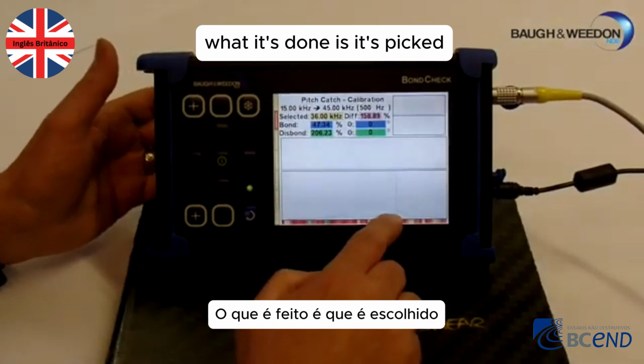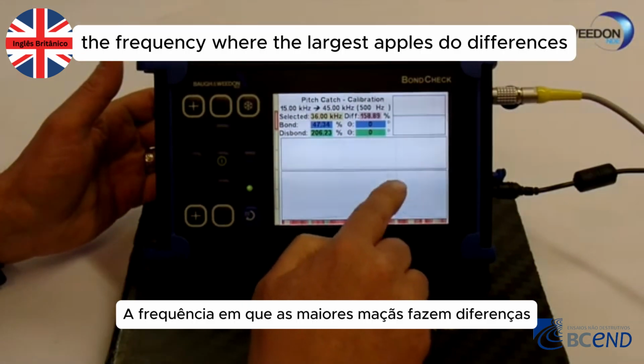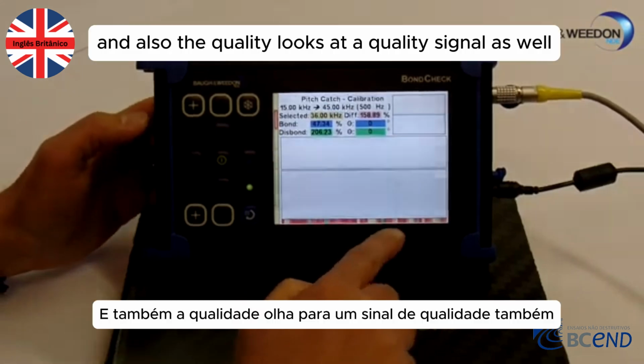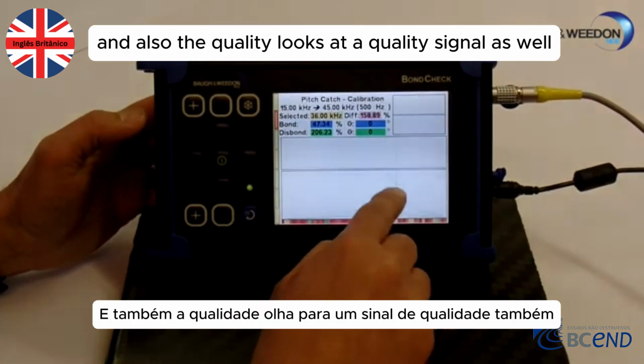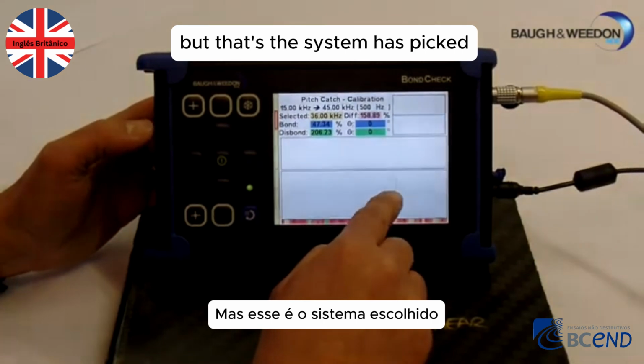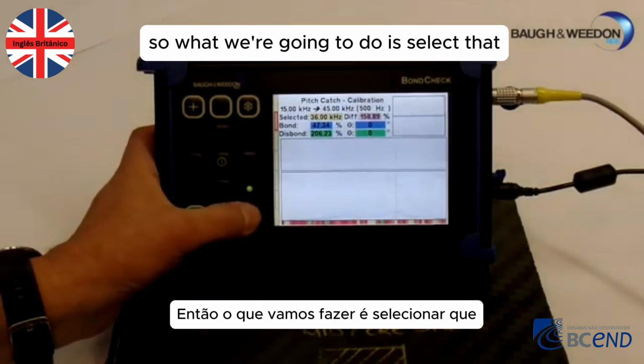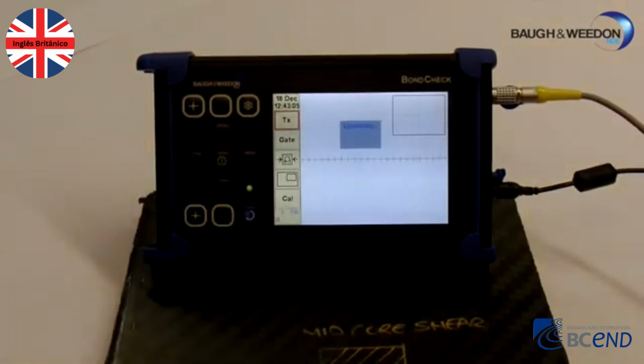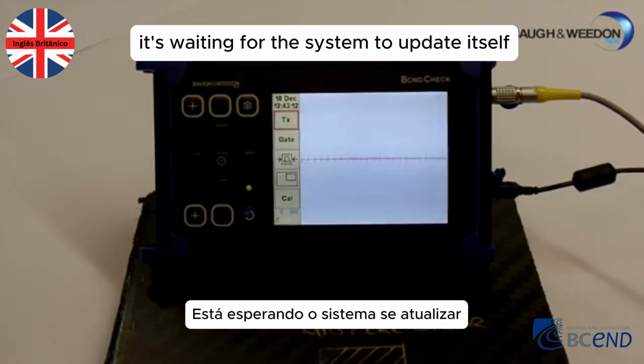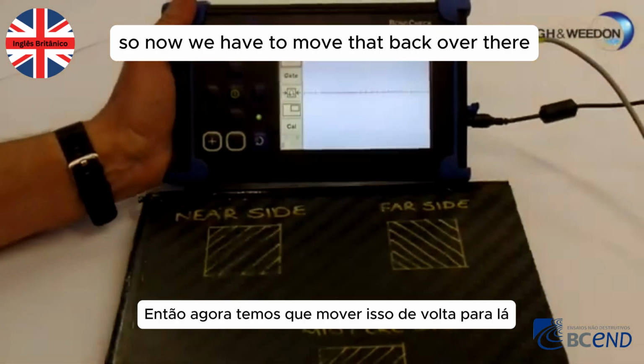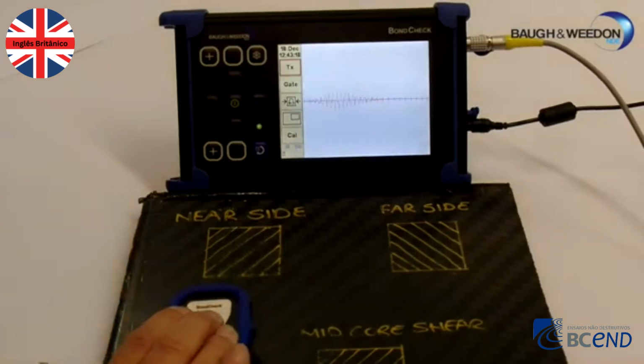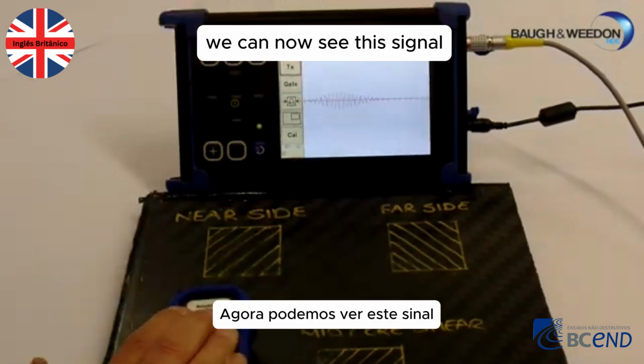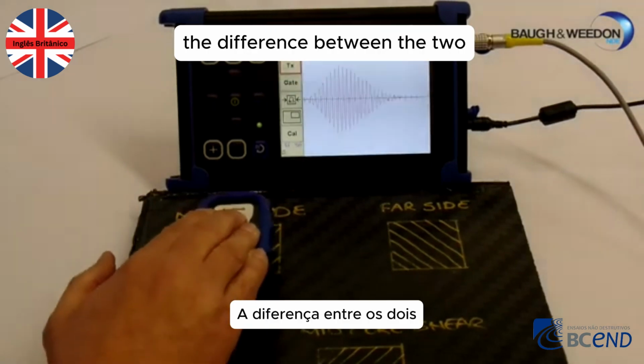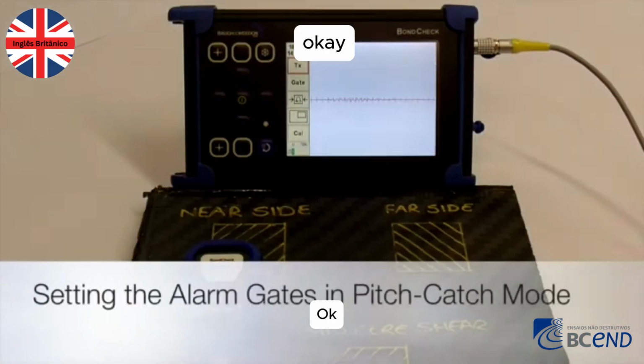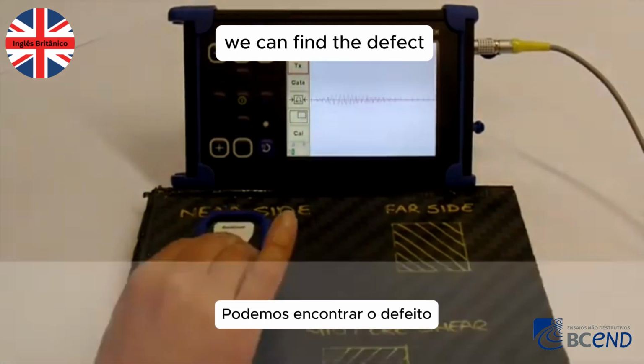What it's done is it's picked the frequency where the largest amplitude difference is, and also the quality. It looks at a quality signal as well. So the system has picked this one as its best option. So what we're going to do is select that. Just waiting for the system to update itself. So now I move that back off of there, put the probe on here, press it down. We can now see the signal and the difference between the two. Okay, so we've now calibrated it so that as we scan we can find the defect.